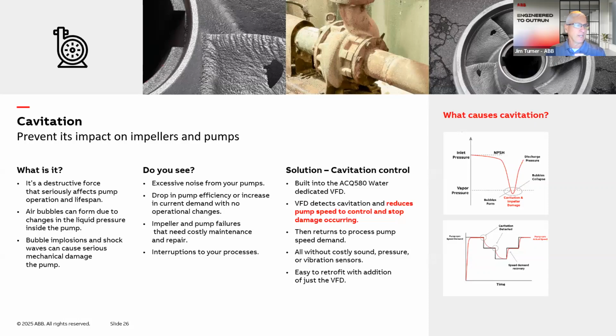So upon the VFD detecting the cavitation event, it can be programmed to slow down the pump and get out of cavitation. And then the VFD will slowly step the speed of the pump up slightly to return back to the commanded speed. Or the VFD can continue to run at the commanded speed and then only alert the operator to the cavitation event. It really depends on the application and the criticality to deliver water in terms of when you would choose one method or the other.